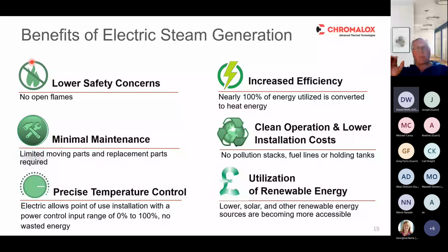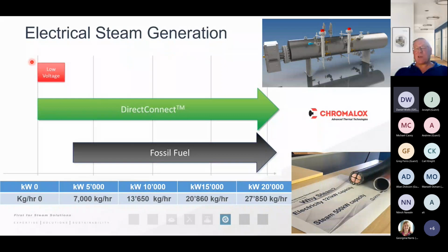But again, we've got to remember that whenever we're generating steam from electricity, there's only so much energy we can get down an electrical cable. So we really need to be satisfied that the infrastructure that's bringing the electricity into the boiler house is capable of providing the electricity that is required instantaneously whenever there's a demand. And that's something that's challenging to do when we compare that to a traditional natural gas steam boiler.